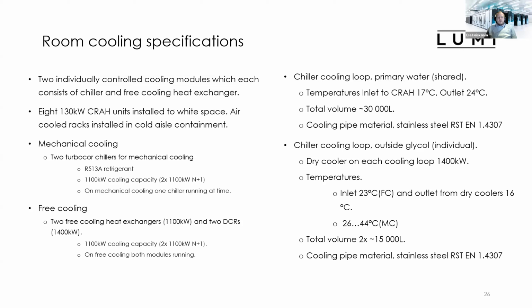So in the mechanical cooling, we are only running 1 chiller at a time. And the free cooling, same way, we have installed 1.1 megawatt of cooling capacity. And in the free cooling, we are running both of these cooling modules to avoid the glycol loop getting too cold in the wintertime. Basically, these are the volumes and the details of what we are running. So 17 Celsius inlet to the CRAH and outlet is 24 degrees, and there are quite huge volumes in these ones.